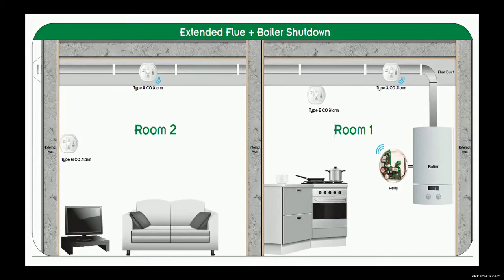So you have a boiler that's brought into a kitchen or a utility room, and then you have the extended flue off that. So in the duct or void that the flue is passing through, you have what they call two Type A devices. A Type A device, a carbon monoxide alarm, is a device that detects carbon monoxide, it sounds, and it also sends a signal to another device to activate. So what has happened here is those two devices are in, because that's not an open ducted void all the way through, it's segmented. So we need one in each segment. But both of those devices are connected to the relay alongside the boiler. So if any of those activate, they will send a signal to the relay and that shuts off the boiler. Okay, so they're your Type A devices.